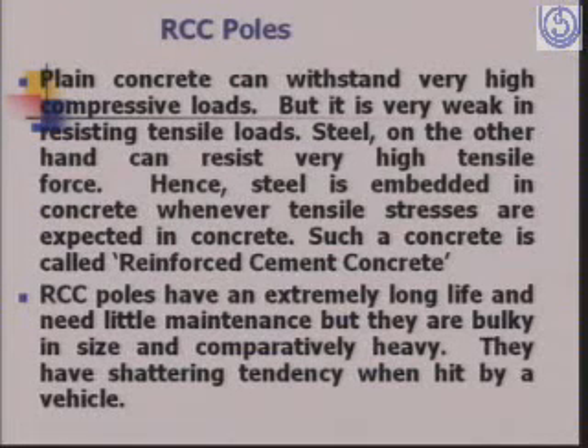Then we have the RCC poles. Plain concrete can withstand very high compressive loads, but it is very weak in resisting tensile loads. Steel, on the other hand, can resist very high tensile force. Hence, steel is embedded in concrete wherever the tensile stresses are expected in concrete. Such a concrete embedded with steel is called reinforced cement concrete pole. The RCC poles have an extremely long life and need little maintenance, but they are bulky in size and comparatively heavy. They have shattering tendency when hit by a vehicle.